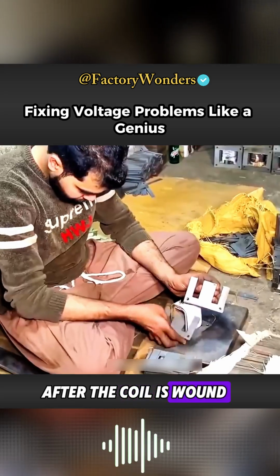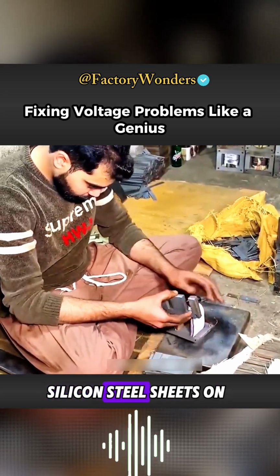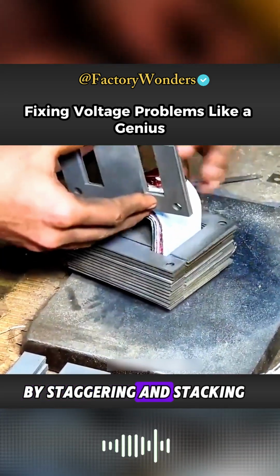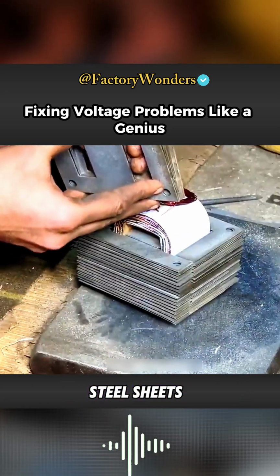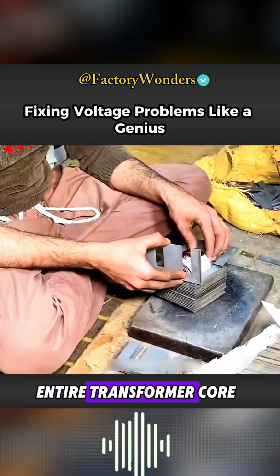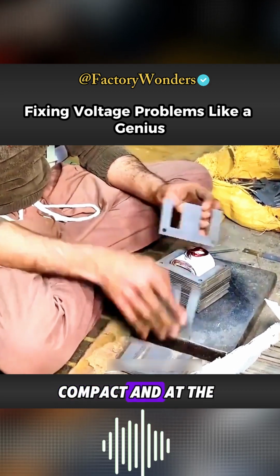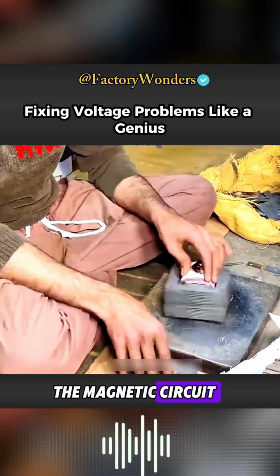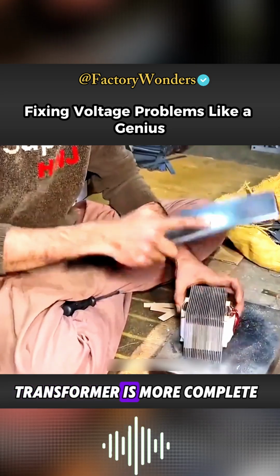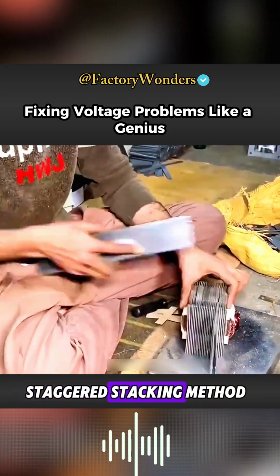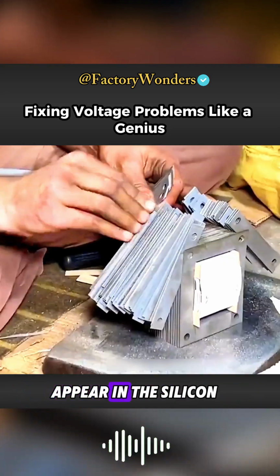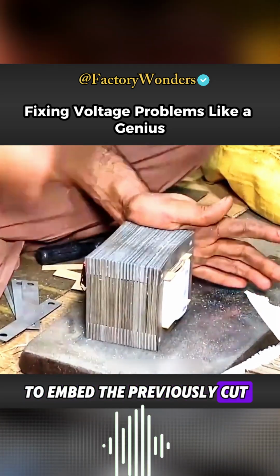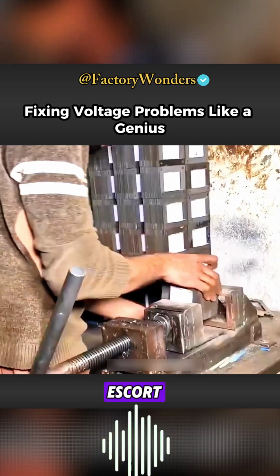After the coil is wound, the worker will embed silicon steel sheets on the coil. By staggering and stacking the special-shaped silicon steel sheets, the structure of the entire transformer core can be made more compact, and at the same time, the magnetic circuit closure of the entire transformer is more complete. But due to the staggered stacking method, a certain amount of gaps will appear in the silicon steel sheets. So it is necessary to embed the previously cut scraps of silicon steel sheets in the gaps.